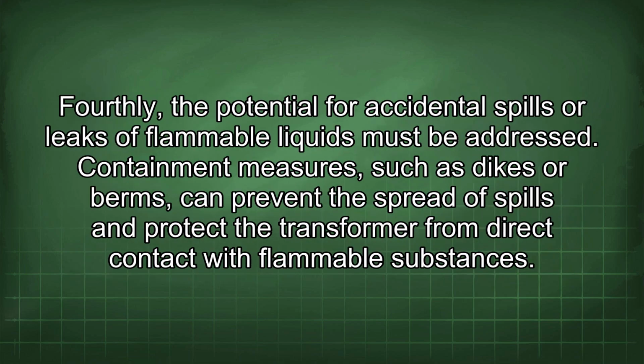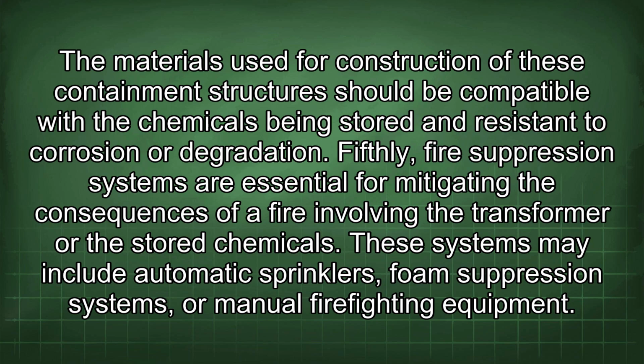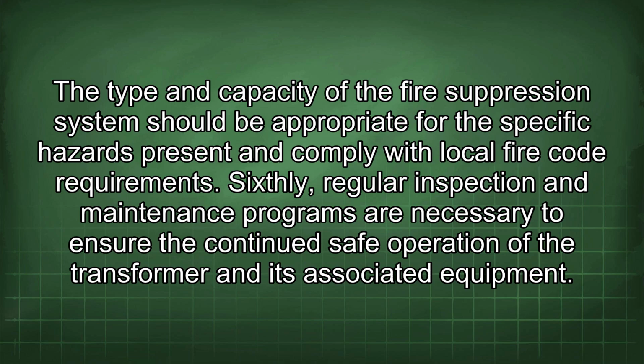Fourthly, the potential for accidental spills or leaks of flammable liquids must be addressed. Containment measures, such as dikes or berms, can prevent the spread of spills and protect the transformer from direct contact with flammable substances. The materials used for construction of these containment structures should be compatible with the chemicals being stored and resistant to corrosion or degradation. Fifthly, fire suppression systems are essential for mitigating the consequences of a fire involving the transformer or the stored chemicals. These systems may include automatic sprinklers, foam suppression systems, or manual firefighting equipment. The type and capacity of the fire suppression system should be appropriate for the specific hazards present and comply with local fire code requirements.